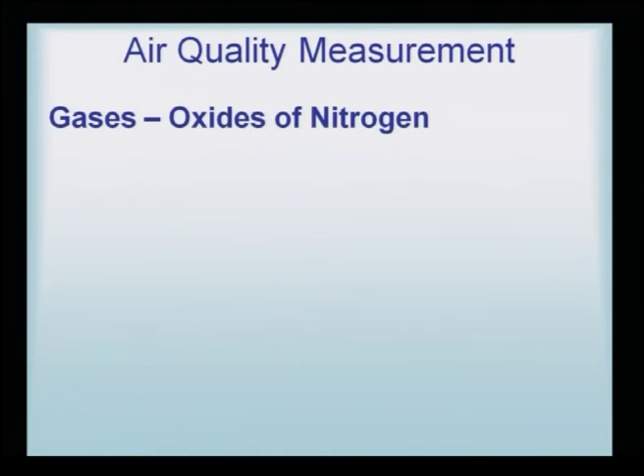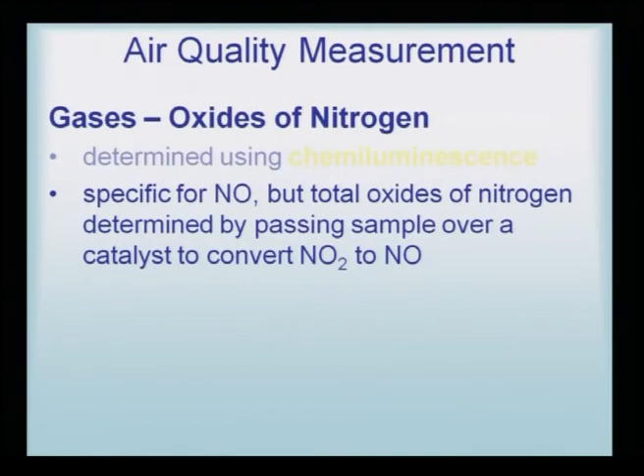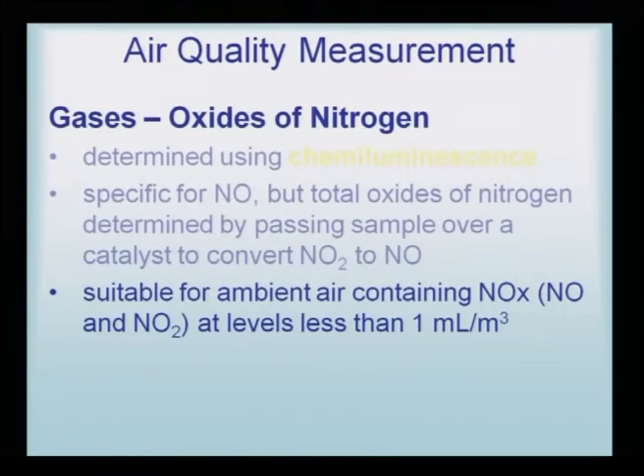Then gases of nitrogen. I have been referring to this as NOx, and it should be kept clearly in mind that there is more than one type of nitrogen oxide to be referred to. It is determined using chemiluminescence specific for NO, that is nitrogen oxide. Total oxides of nitrogen are determined by passing the sample over a catalyst to convert NO2 to NO. So, it is only analyzing one particular species, NO, and all the nitrogen dioxide is first converted into NO and then analyzed. It is suitable for ambient air containing NOx, that is both NO and NO2, at levels less than 1 milliliter per cubic meter.